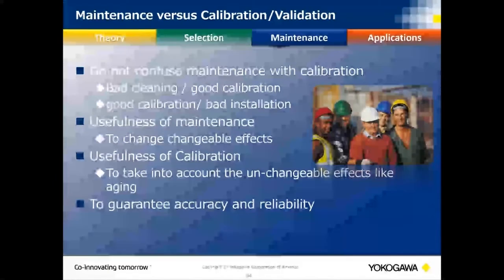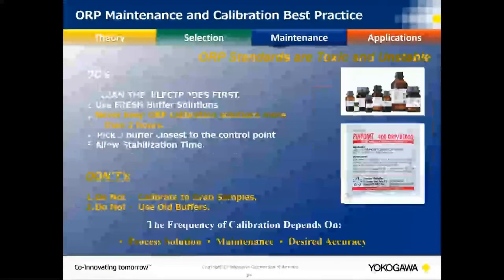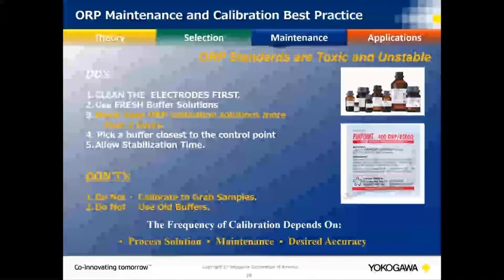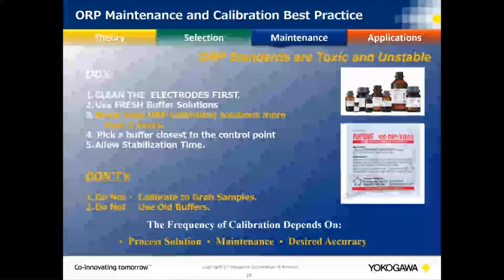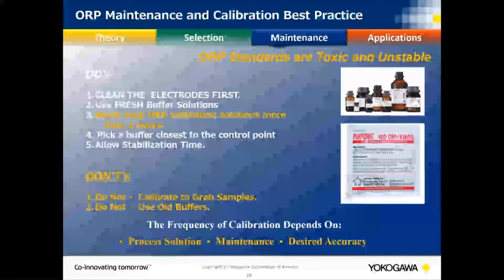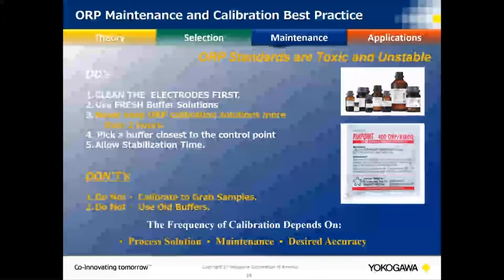Now for maintenance and calibration — the fun part. Calibration and validation are different. If we don't have good cleaning, we won't have good calibrations. Always start with cleaning. Known best practices include: clean your electrodes first, use fresh buffer solutions, never keep ORP calibration solutions more than two hours as they're not stable and can get contaminated quickly.